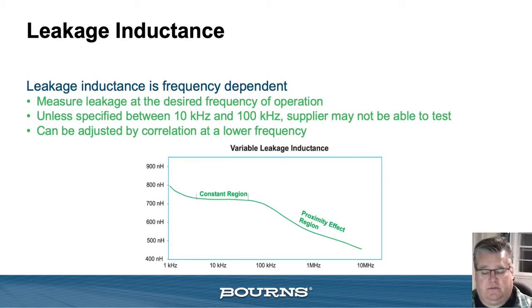Typical suppliers will give you leakage inductance in terms of the constant region, usually between 10 kilohertz and 100 kilohertz. But that doesn't necessarily help you if your switching mode of operation may be 200 to 500 kilohertz for your supply, or if you're looking to accurately depict EMI or conducted emissions through the transformer - you may be looking at a much higher frequency than that.